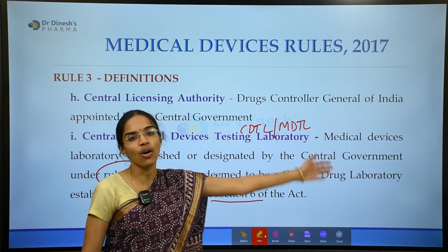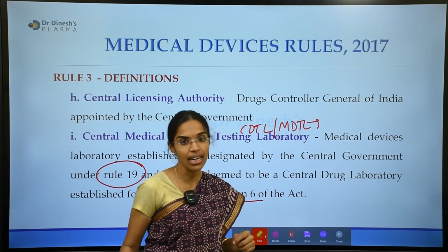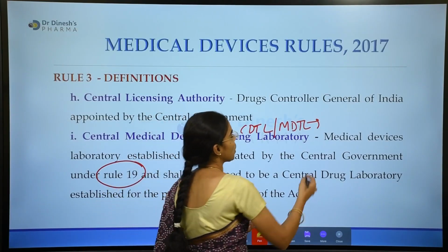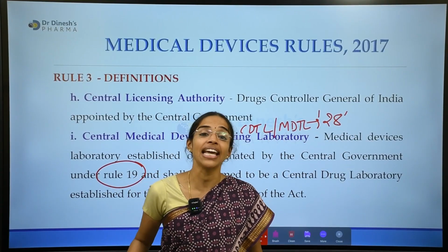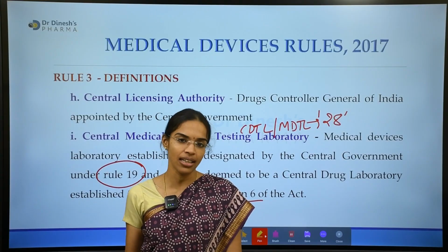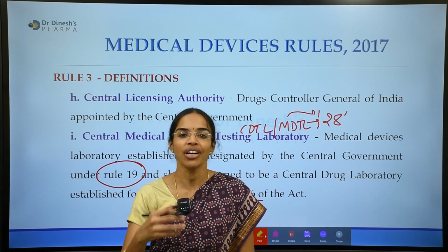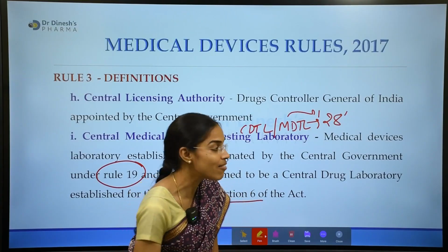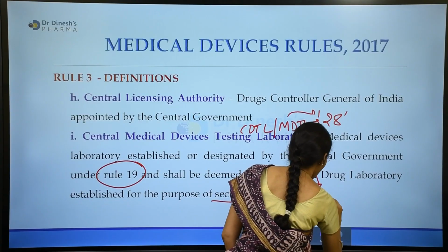So there are several MDTLs or CDTLs approved by the Government of India, and as per the current notice, there are totally 28 Central Device Testing Laboratories or Medical Device Testing Laboratories currently functioning in India. Along with MDTLs, we also have RDTLs. This is also important here.